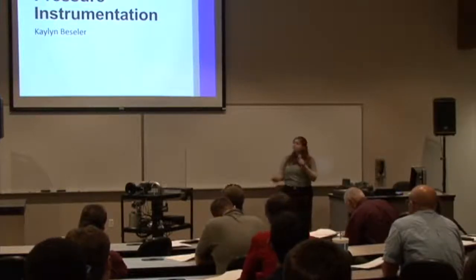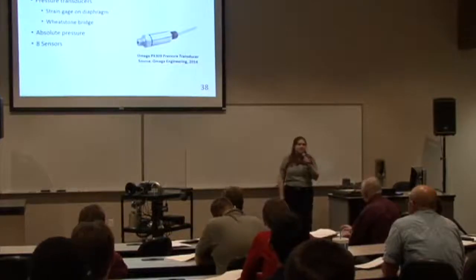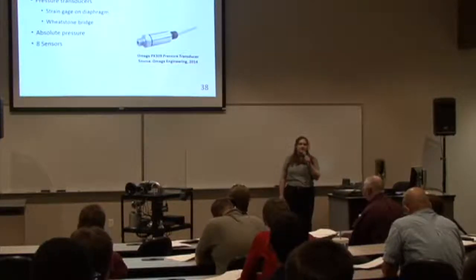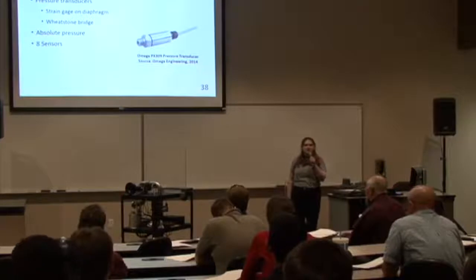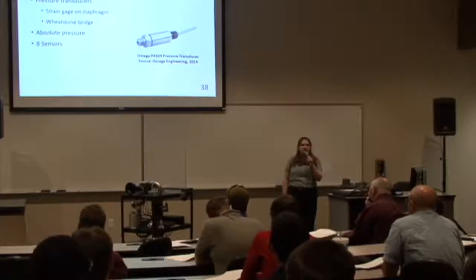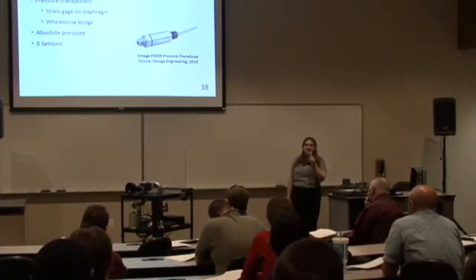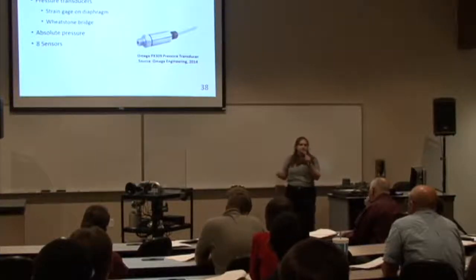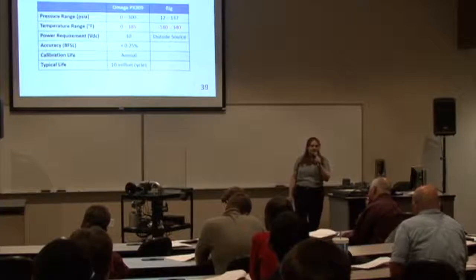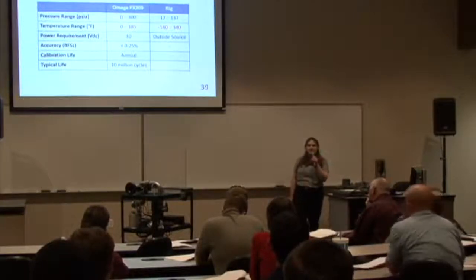Thank you, Josh. The pressure sensors selected for the rig are the Omega PX309. These are pressure transducers that utilize a strain gauge on a stainless steel diaphragm and a Wheatstone bridge setup. These sensors measure absolute pressure, and a total of 8 sensors are used on the rig. This is a table comparing the specifications of the rig to the specifications of the sensors.